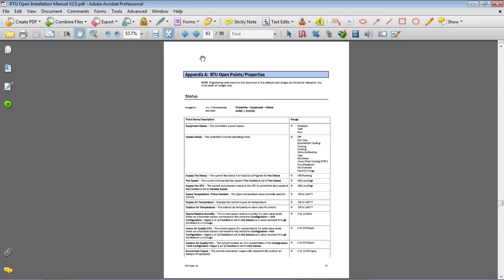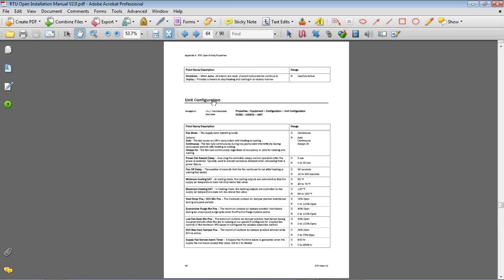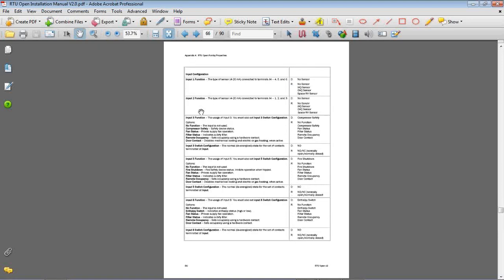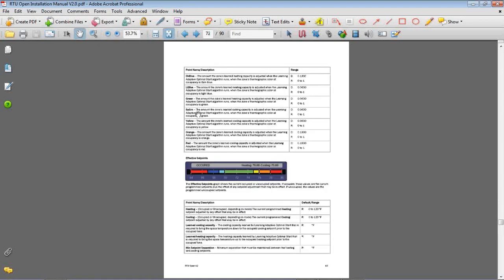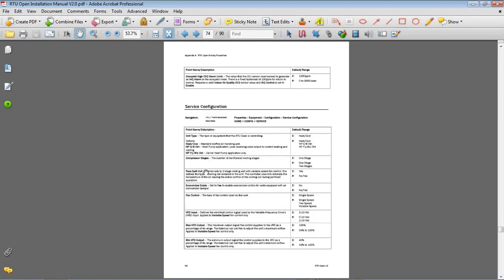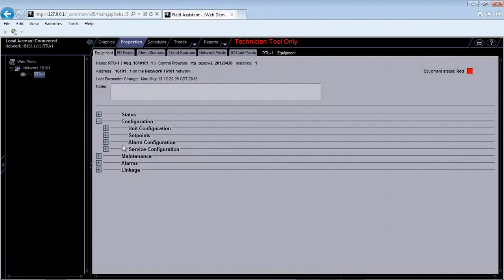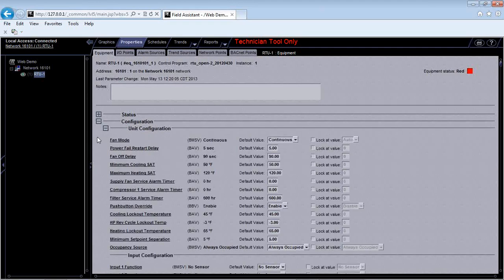Yeah, you'll see here, this is Appendix A of the installation manual. You can see that I have each of those drop downs. So I have status right here. It will tell me the different statuses I can have and what they mean, what I configure them for. I have unit configuration like we saw, all the different inputs that you can change. I have set points. I have alarm configuration and service configuration. Okay, so if you ever have a question or you forget what we talked about here on one of these tables, you can reference the installation manual to see what exactly you need to set for that specific item. Okay, so we're going to start with unit configuration and work our way down.